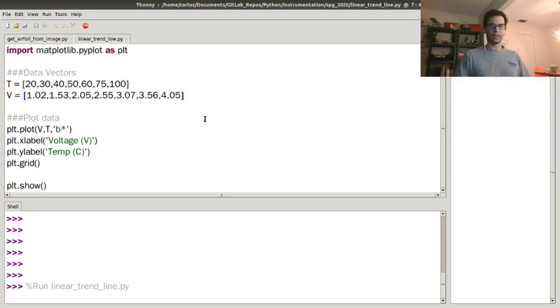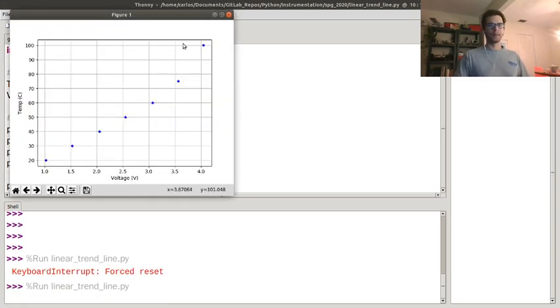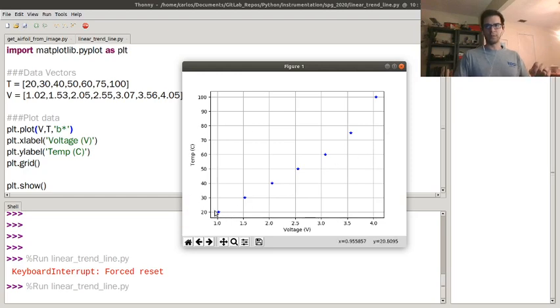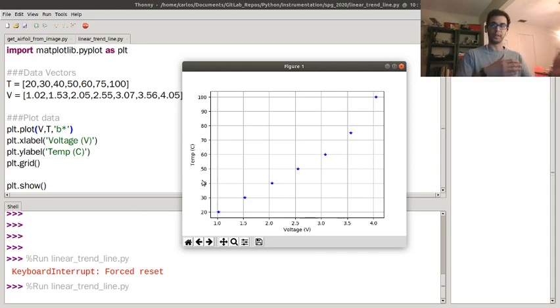If I hit F5 here — there we go. So you get this plot. The problem is that you have a thermocouple and you're trying to calibrate it. The idea is that you put a thermocouple in at a certain temperature, and you have another sensor that's measuring temperature. So basically you need two sensors: a thermocouple that's uncalibrated, and a temperature sensor that is calibrated.